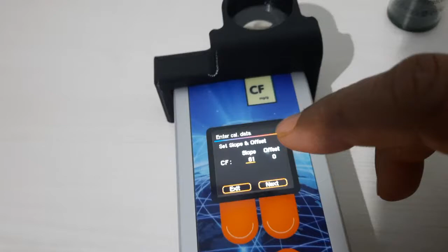Enter, exit, put the vial here, measure. 1.48, so we have to increase it a little bit. Menu, enter. Sensor settings, enter. Calibration data, enter. So that we have to set the slope at 55. Next, set, exit, measure.